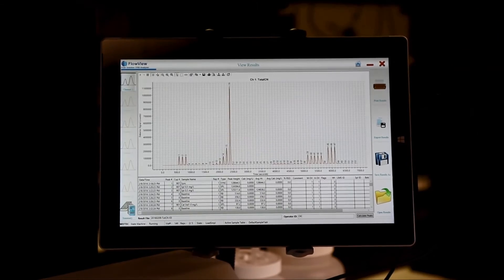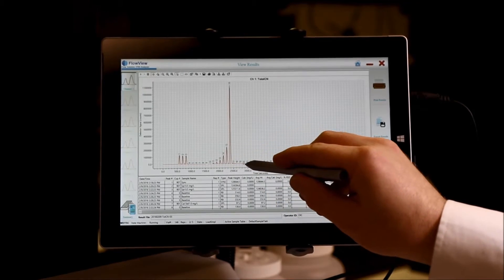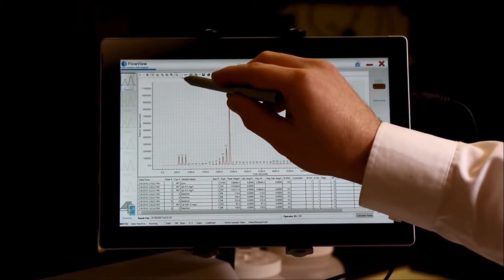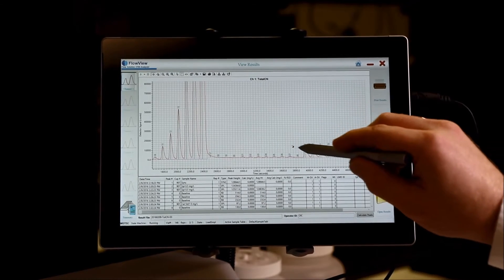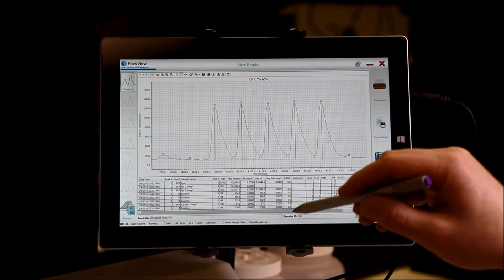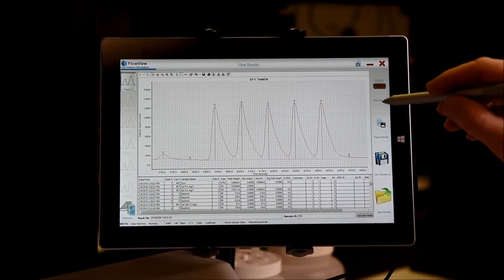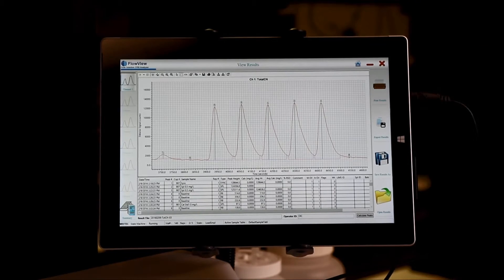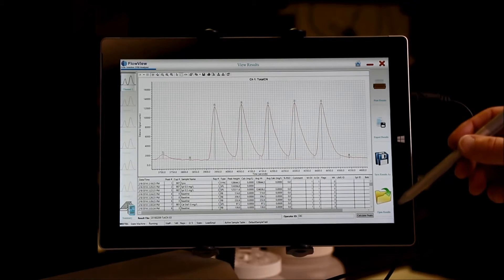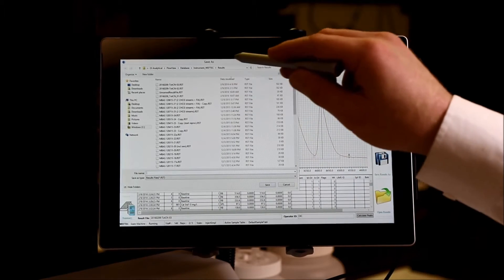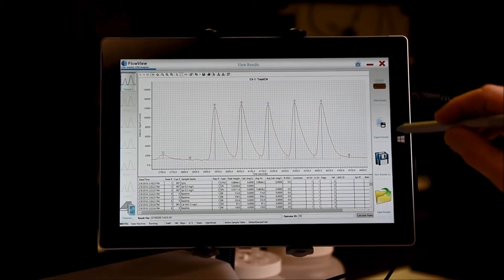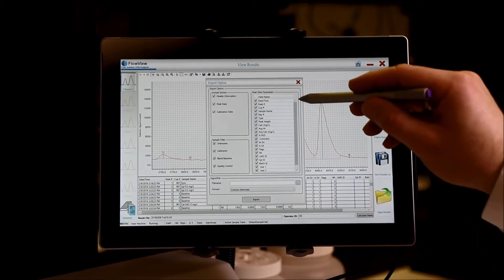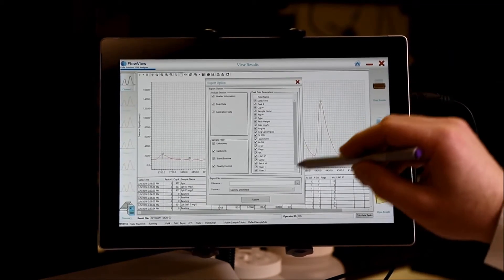We can switch from height to area after the fact, correct issues with peak marking, monitor any quality control parameters that were set during the run, and also make adjustments to peak discrimination. Once all of these things have been modified, the good news is there's no changes to the original data file. There is no save button over here, there's only a save as. Those changes can be saved anywhere on your network or to the local PC, as well as data can be exported anywhere onto your network so that it may be uploaded to your LIMS.